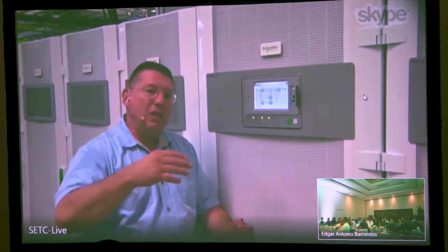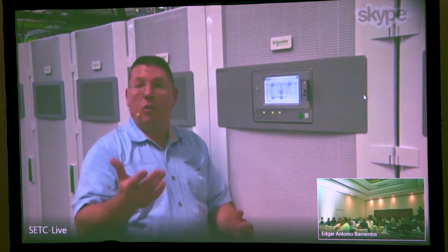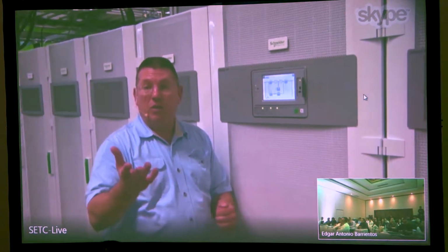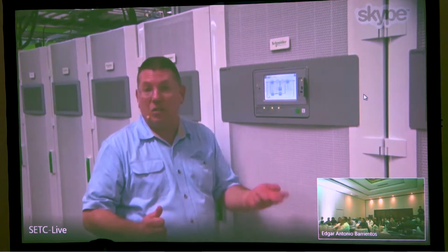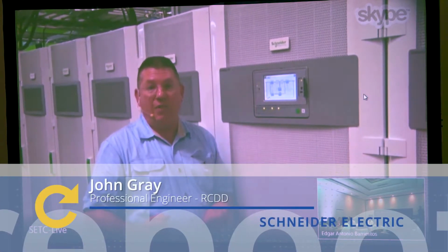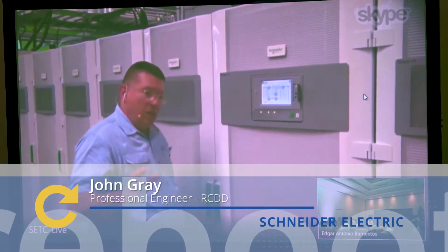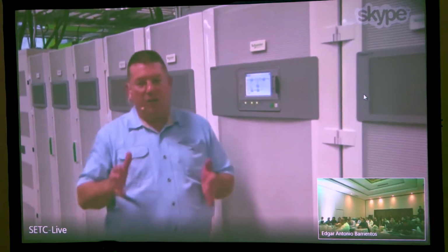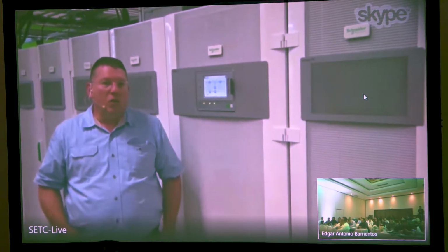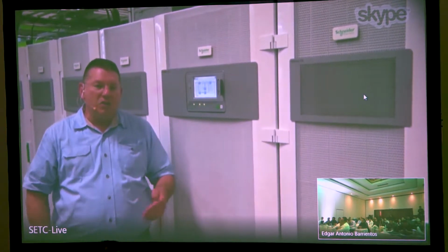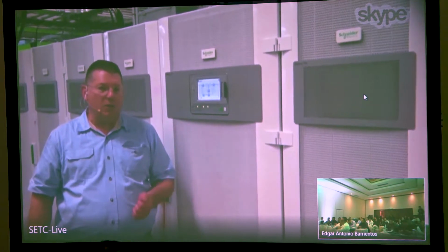What I want to show you is that the fans can be replaced while the unit's carrying load. I'm going to go to one of these cabinets and simulate the loss of a fan, and you'll see the alarms we get. Then we'll show how easy it is for somebody qualified with access to the power room to replace that fan. This is really, in my opinion, a phenomenal feature, because on a legacy unit it can be quite time-consuming and service interrupting to replace a fan.